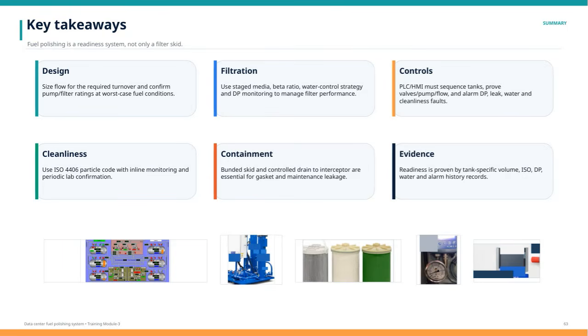Let's go over the key takeaways for fuel polishing systems. First, it's important to remember that fuel polishing is more than just a filter skid. It's a comprehensive readiness system. When it comes to design, we need to size the flow to achieve the required turnover and verify that pump and filter ratings can handle the worst-case fuel conditions.